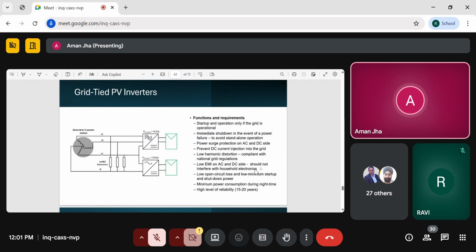Your electronics should work in such a way that they optimize all four. Whenever the panel has power, it takes power from the panel. If the battery is not charged, it charges the battery or supplies power to the load, and excess power can be supplied to the grid. At the same time, if there is no sunlight for maybe 3-4 or 5 days, power should come from the grid to charge the battery. Sometimes, maybe at night, it takes power from the battery to give power to the load. So this optimization is much more complex here.